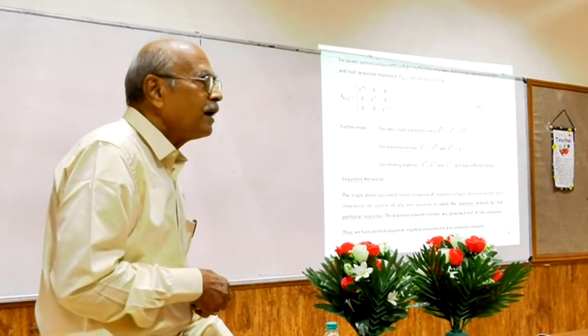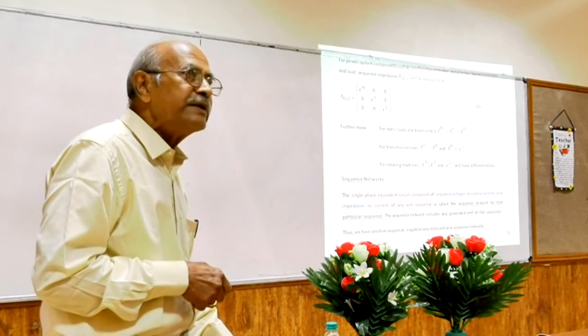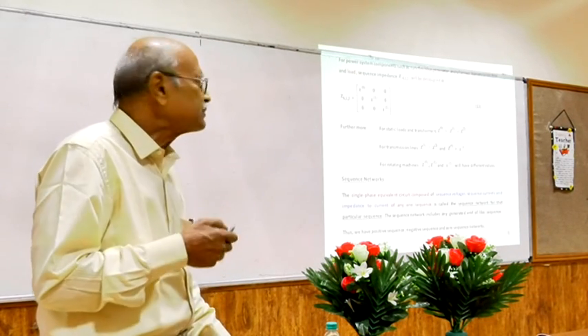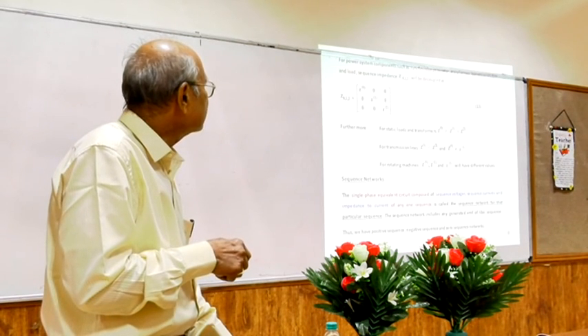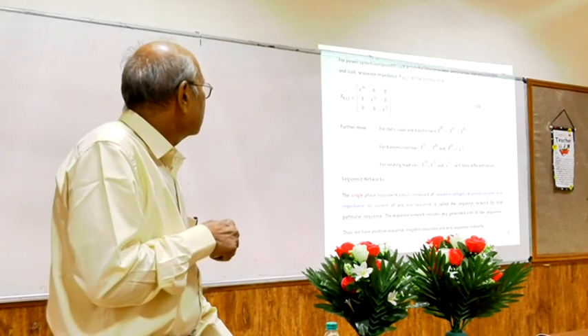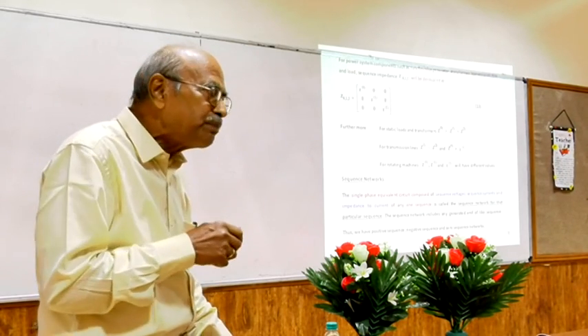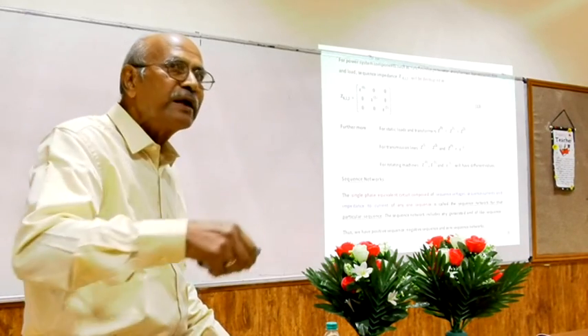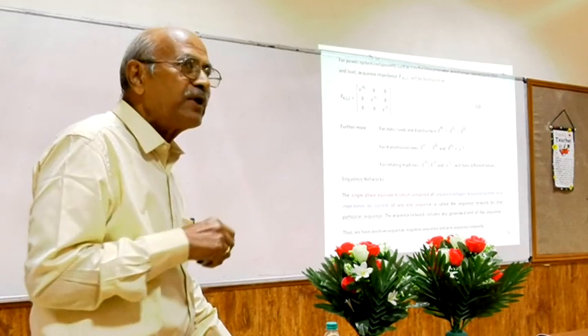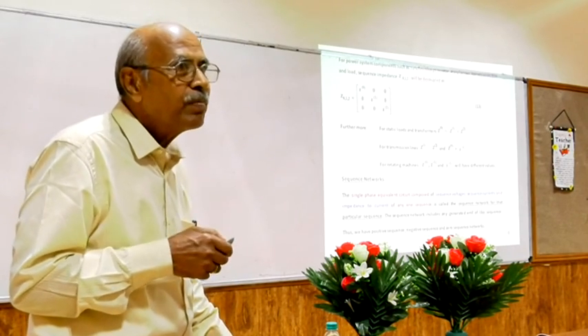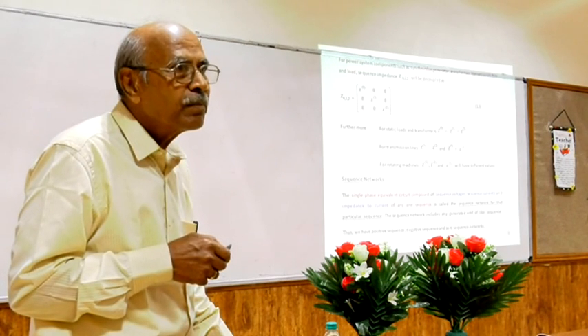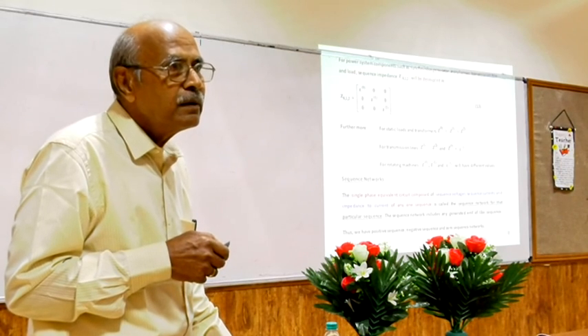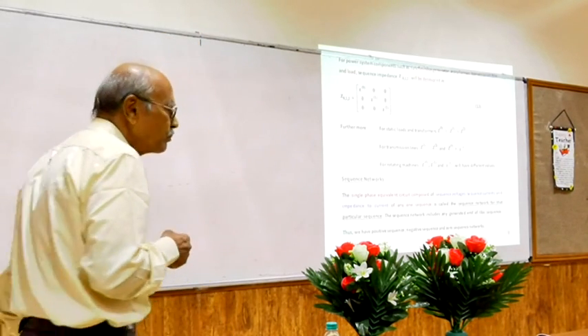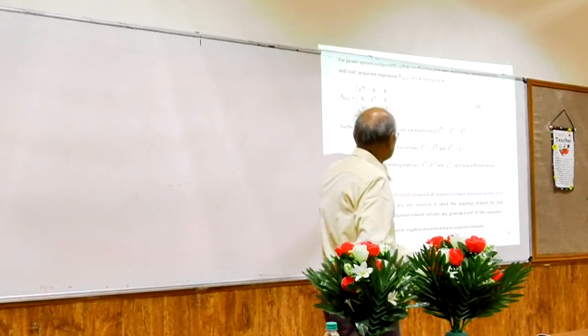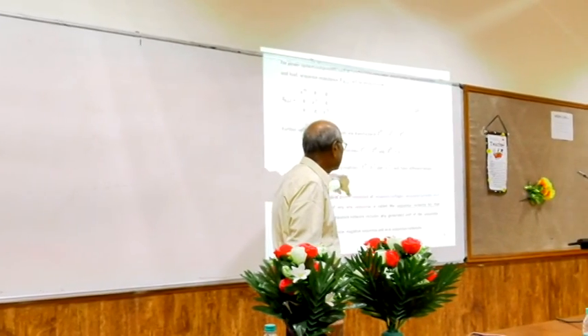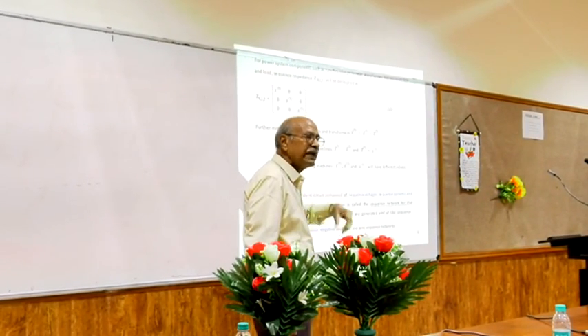Now, fortunately, there is some more additional simplified information. After all, in a power system we have certain generators, transformer, transmission line, and load. In all these cases, the sequence impedance will be decoupled. What do you mean by that? All the off-diagonal terms will be zero. Sir, if it is a generator, then you don't have the same set of impedance for the positive and negative impedance. I am coming to that. If it is a rotating synchronous generator or synchronous motor, then you have Z0, Z1, and Z2. Generally all of them will have different values.